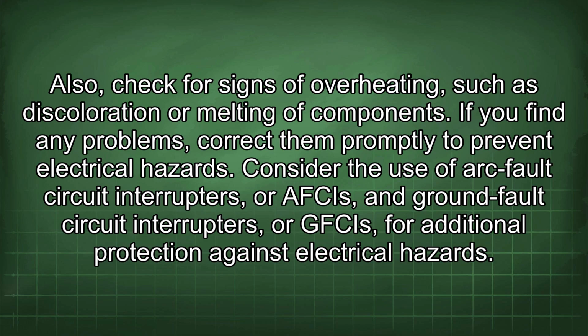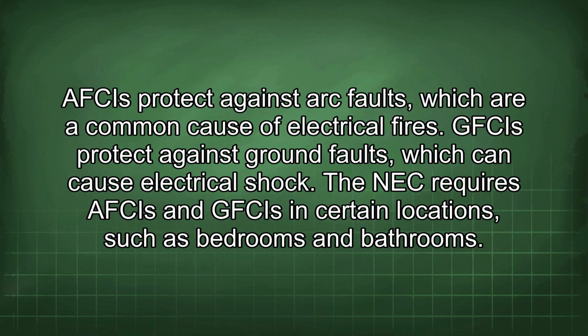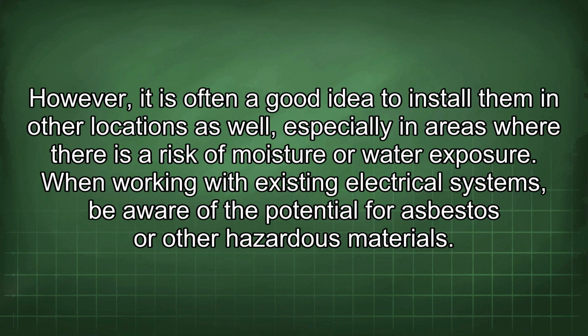Consider the use of arc fault circuit interrupters, or AFCIs, and ground fault circuit interrupters, or GFCIs, for additional protection against electrical hazards. AFCIs protect against arc faults, which are a common cause of electrical fires. GFCIs protect against ground faults, which can cause electrical shock. The NEC requires AFCIs and GFCIs in certain locations, such as bedrooms and bathrooms. However, it is often a good idea to install them in other locations as well, especially in areas where there is a risk of moisture or water exposure.